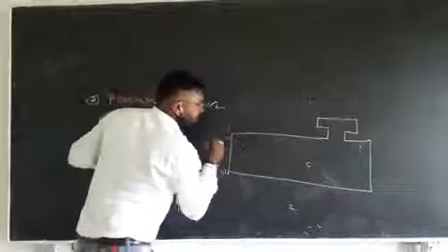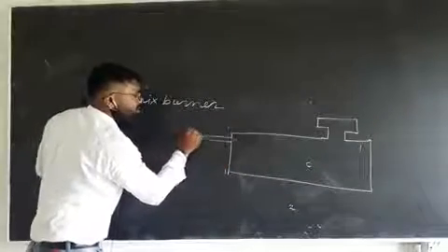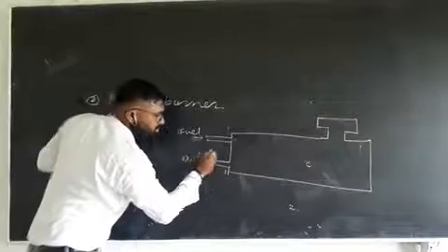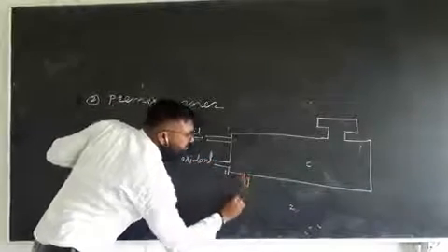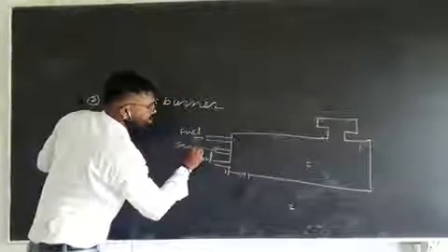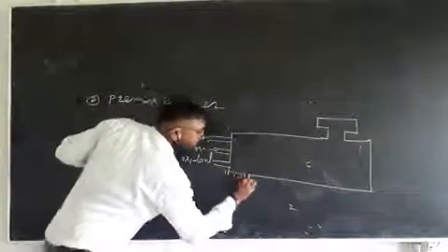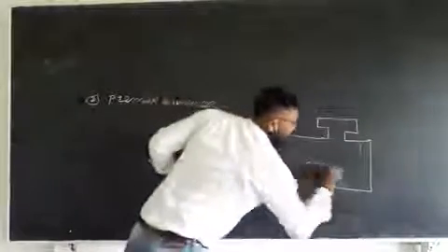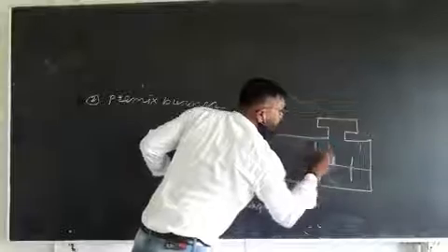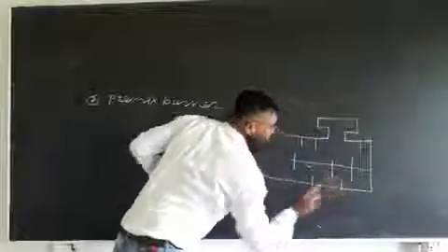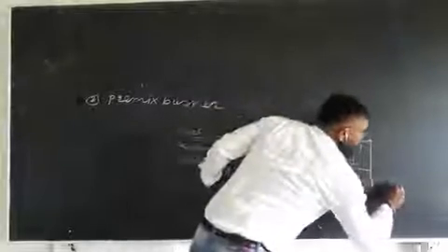There are inlets, one for fuel, second for oxidant, third for sample, and then here is a drain. Inside the premix burner, mixing baffles are used for mixing the fuel and oxidant. These are the mixing baffles.